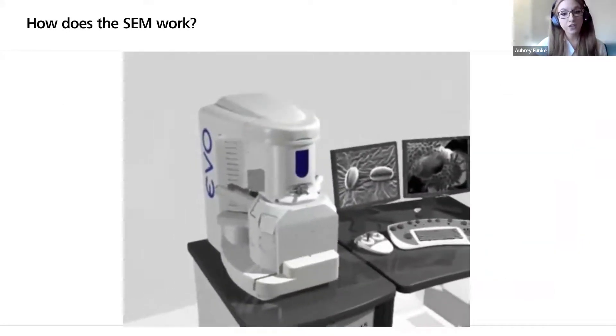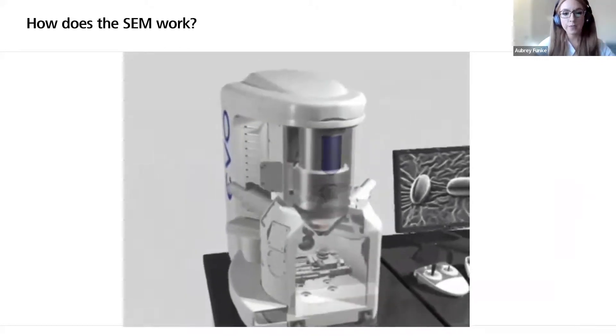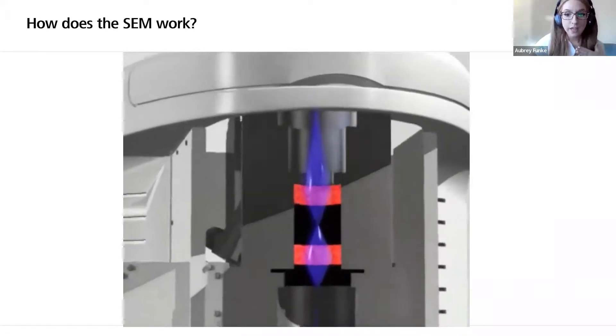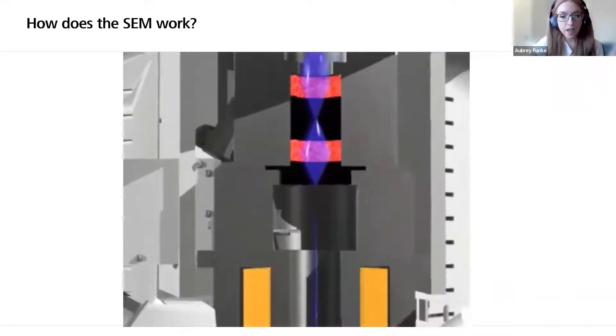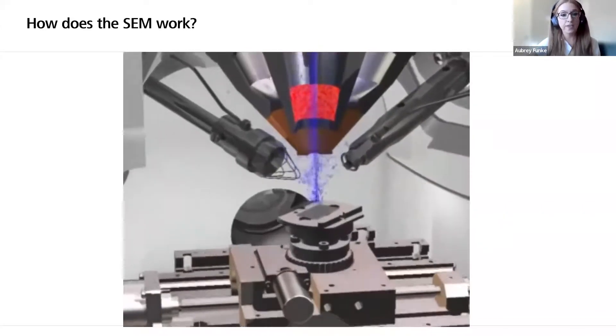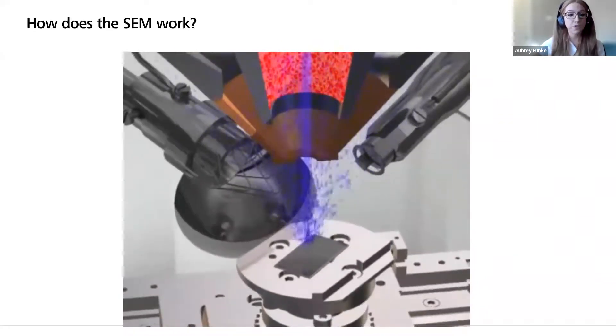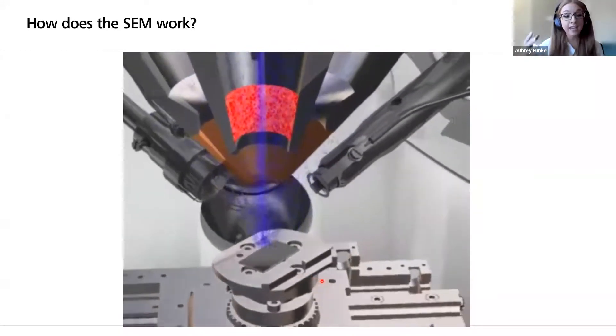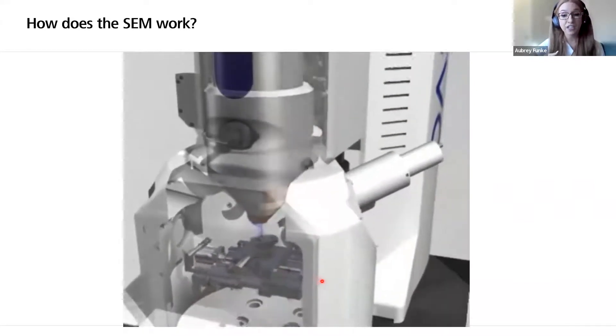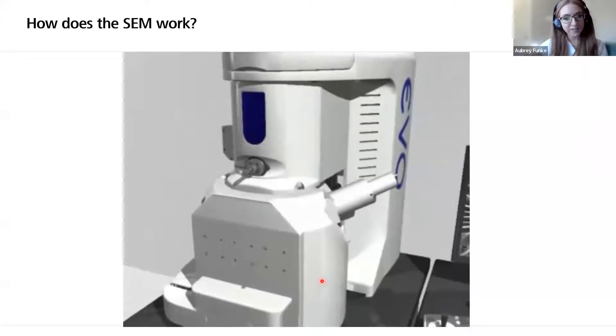Here is a quick animation for how the SEM works. This is a virtual cross-section of the column, with the electron beam colored blue. That electron beam is generated by the gun at the top of the column, then those electrons are accelerated through the column, which consists of electron optics and apertures that finally focus that beam and direct it onto the sample sitting in a specimen chamber just below the final lens. As that beam is scanned or rastered across the sample, a variety of electrons, photons, and x-ray signals are generated, collected by detectors, and converted into a digital image on the screen.